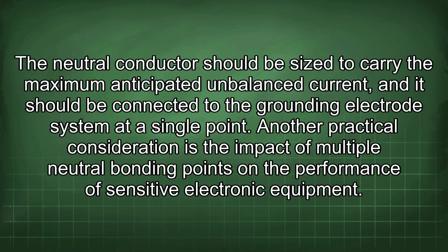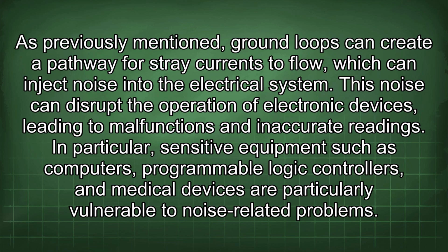The neutral conductor should be sized to carry the maximum anticipated unbalanced current, and it should be connected to the grounding electrode system at a single point. Another practical consideration is the impact of multiple neutral bonding points on the performance of sensitive electronic equipment. As previously mentioned, ground loops can create a pathway for stray currents to flow, which can inject noise into the electrical system. This noise can disrupt the operation of electronic devices, leading to malfunctions and inaccurate readings.